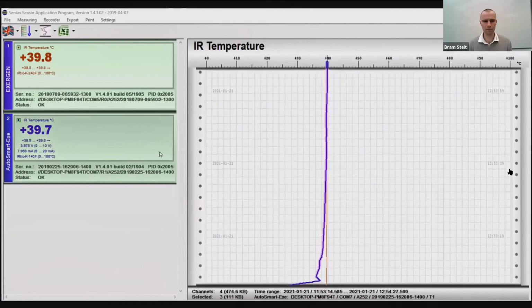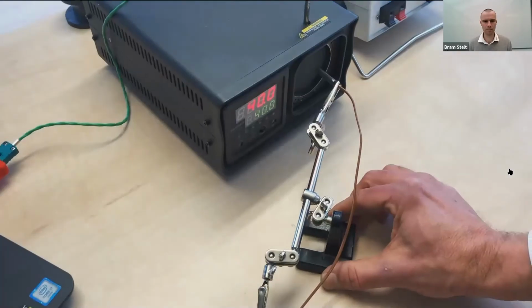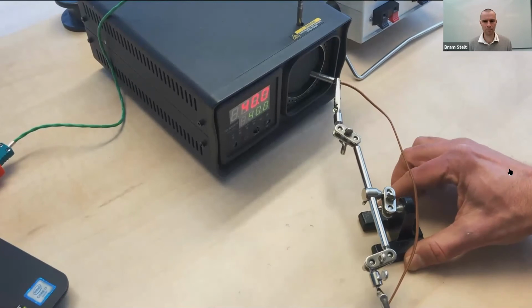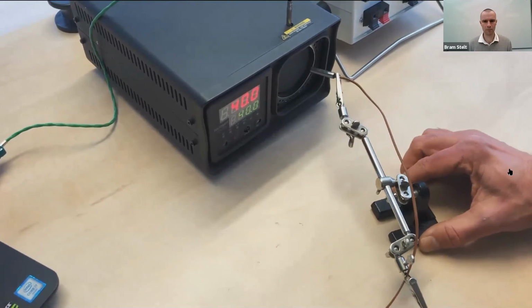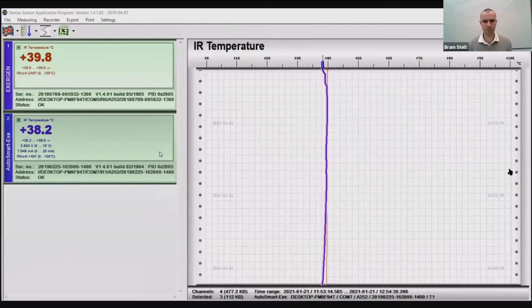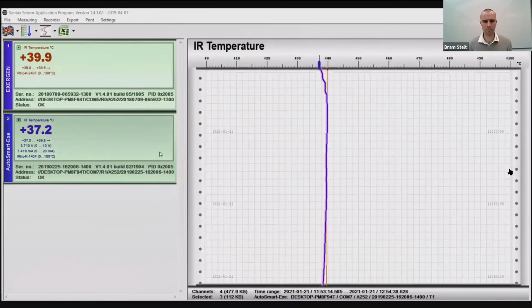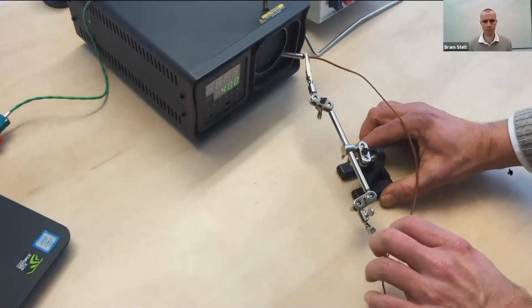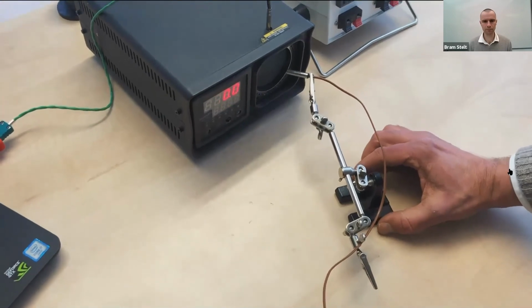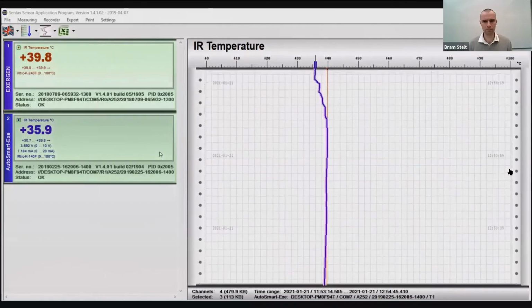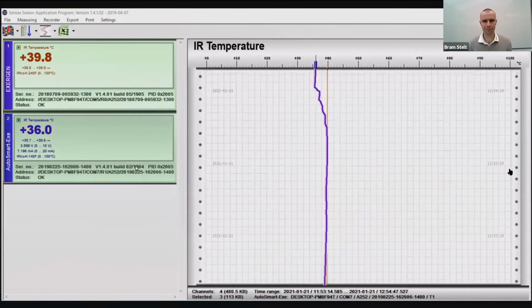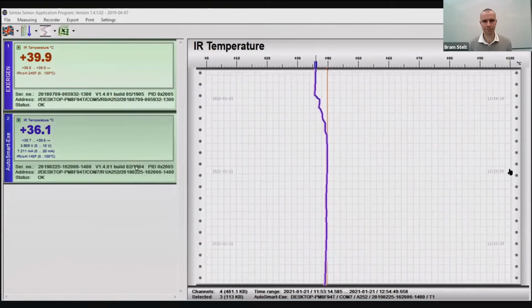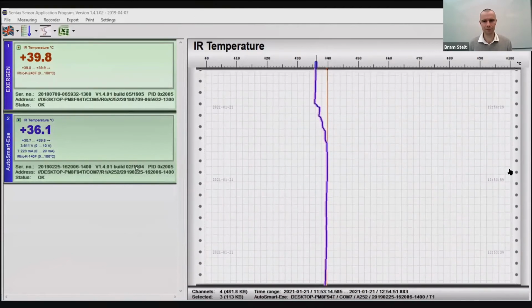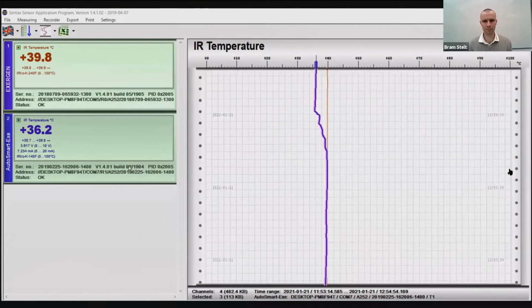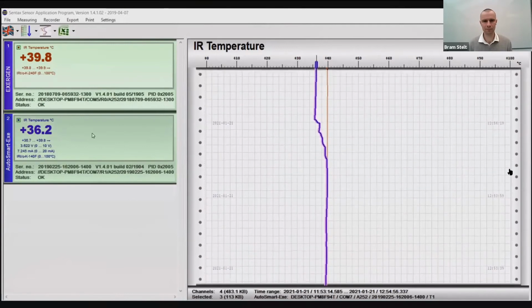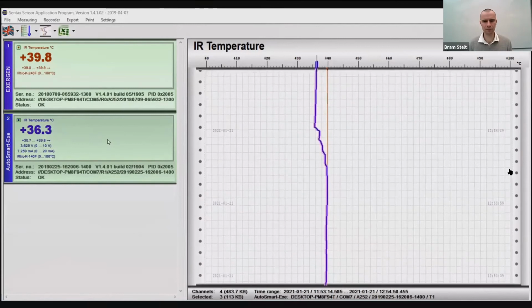But in this case, just for the sake of example, I'm going to put the sensor at an angle. Let's say you have an application where the sensor is maybe measuring obliquely. Now you immediately see an effect in the reading, where the sensor now, because of field of view issues, is giving a different reading than the target and the black body, because there are other things in the field of view that affect the reading. But I can adjust for this. Let me show you how that works.